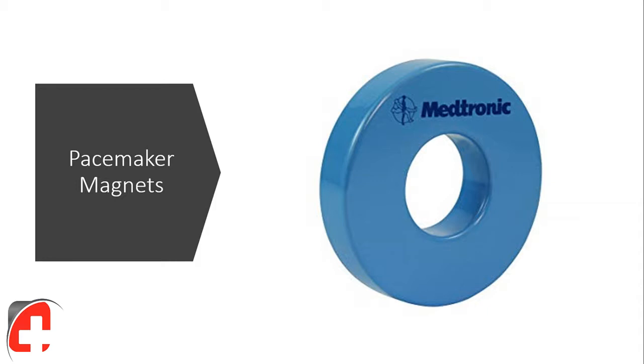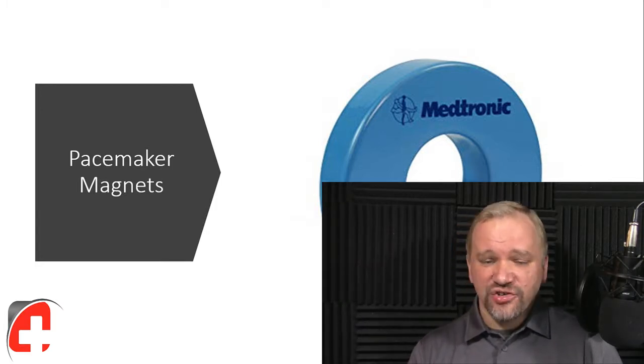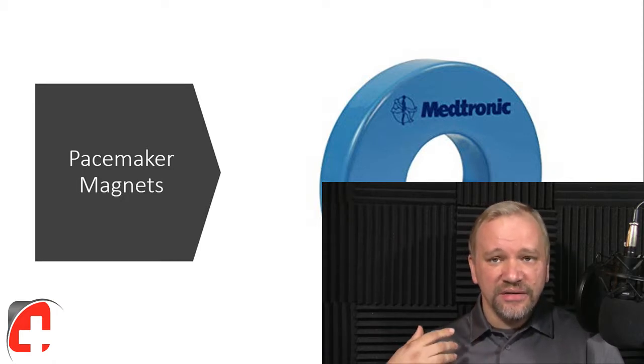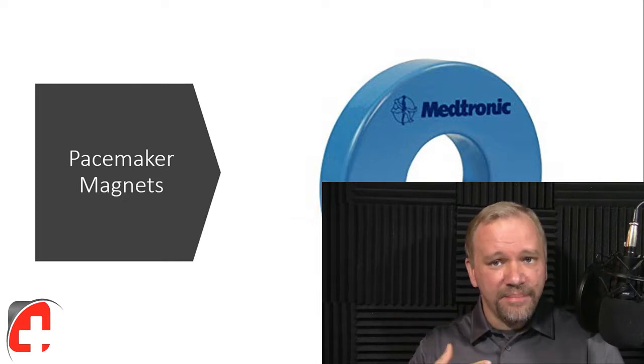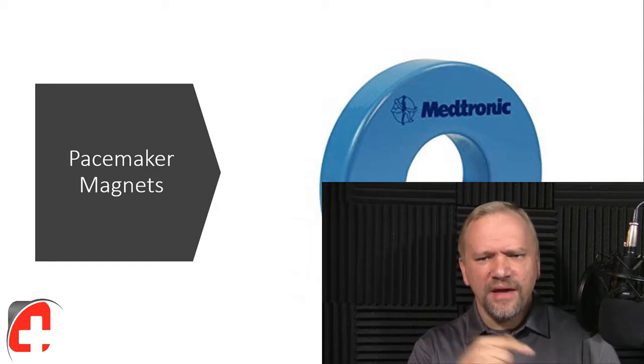One of the other features of pacemakers, ever since they added additional modes, is that they all have pacemaker magnets that can be used with this. Now, what's the utility of a magnet? Well, a magnet can change the mode that the pacemaker is pacing in. If you think about a VNS stimulator, a VNS stimulator will actually, if you put the magnet right over the stimulator, it will actually trigger the device to stop a seizure. So this actually sort of works like that, but the opposite.